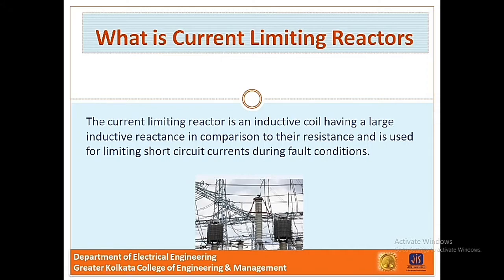The forces on the turns of this reactor under short circuit condition are considerable, and therefore the windings must be solidly braced. It may be added that due to the very small resistance of the reactor, there is very little change in the efficiency of the system.